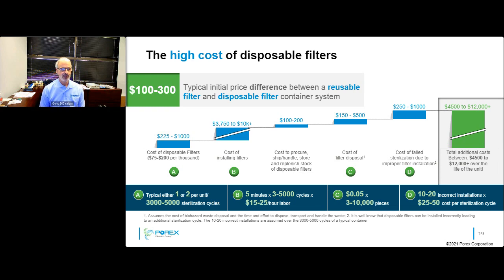But if you start looking at the nuts and bolts of it, so you start on the left, what is the cost of these disposable filters? These things tend to cost between $75 and $200 per 1,000 filters, right? So if you're saying a typical product lasts between 3,000 and 5,000 cycles, that can be between $225 and $1,000 just for the filters, just to buy the filters.